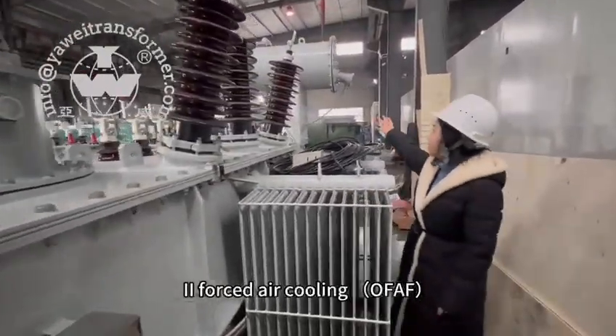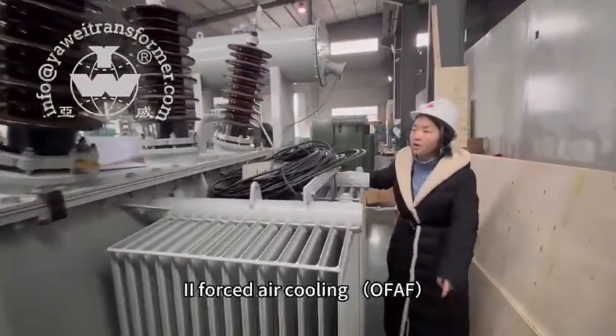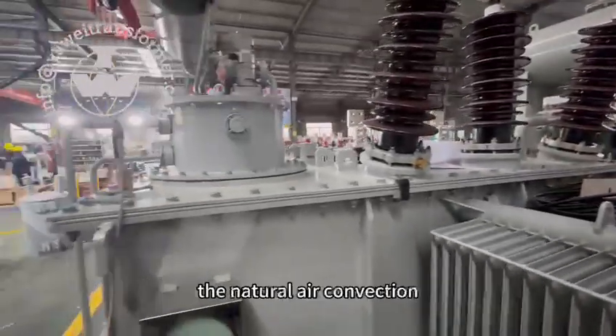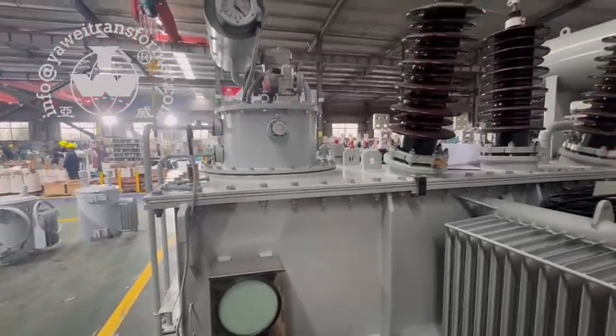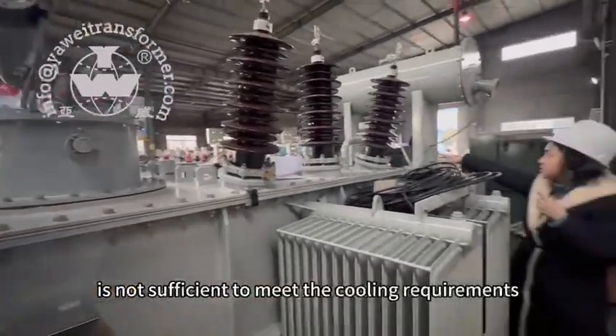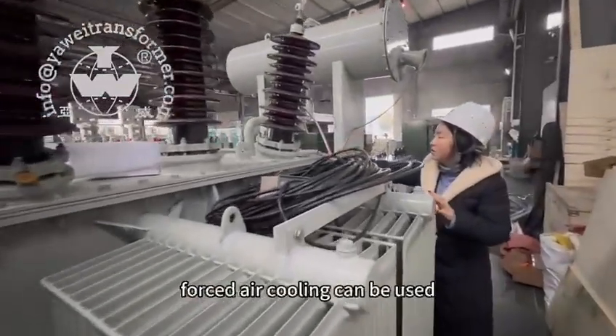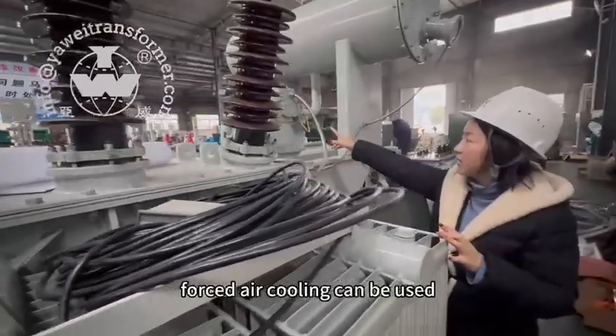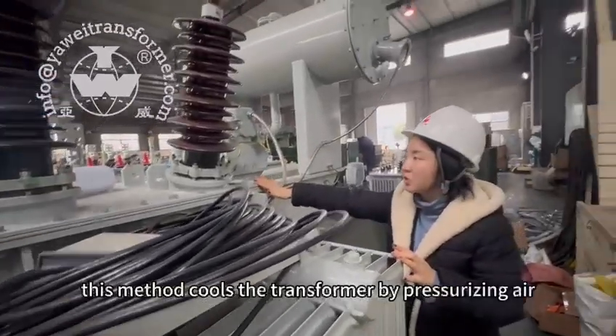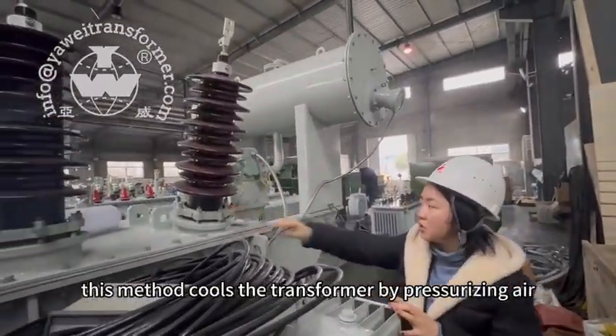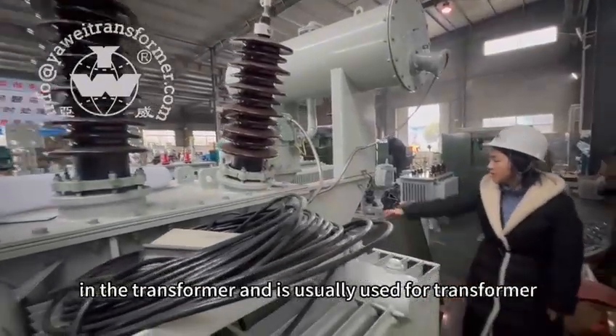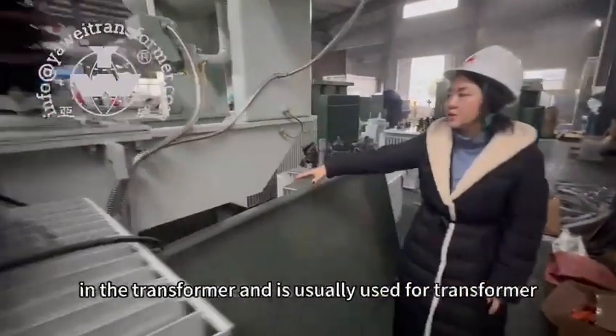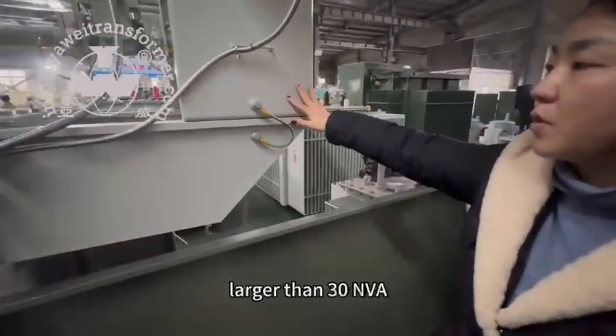Second, forced air cooling, OFAF. When the capacity of the transformer increases, the natural air convection is not sufficient to meet the cooling requirements, so forced air cooling can be used. This method cools the transformer by pressurizing air in the transformer and is usually used for transformers larger than 30 MVA.